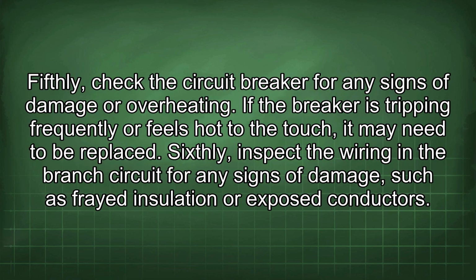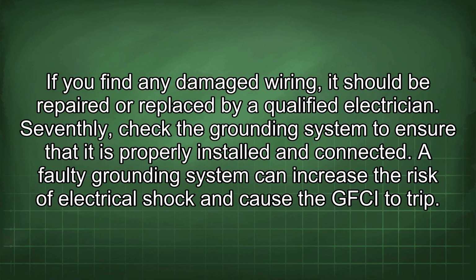Fifthly, check the circuit breaker for any signs of damage or overheating. If the breaker is tripping frequently or feels hot to the touch, it may need to be replaced. Sixthly, inspect the wiring in the branch circuit for any signs of damage, such as frayed insulation or exposed conductors. If you find any damaged wiring, it should be repaired or replaced by a qualified electrician.